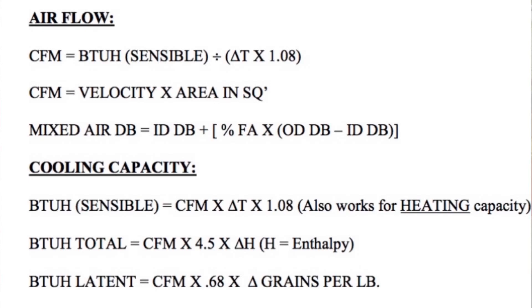Back to cooling capacity: CFM times 4.5 gives you total cooling capacity — latent and sensible combined — when you also multiply by delta H. Delta T is your sensible temperature: air going in at 70°F and coming out at 115°F is a 45-degree delta T. With delta H you're accounting for the latent cooling as well — it's your total heat. To get delta H you need something that measures both relative humidity and sensible temperature, or that measures enthalpy directly.